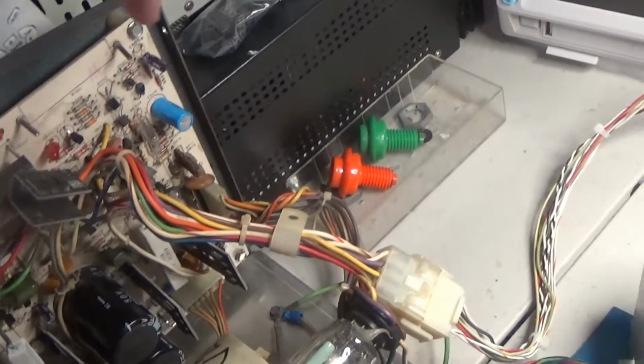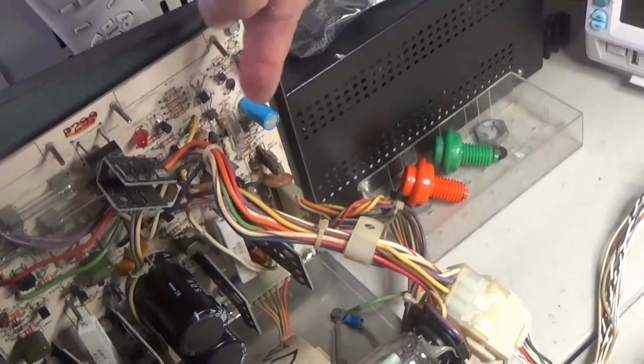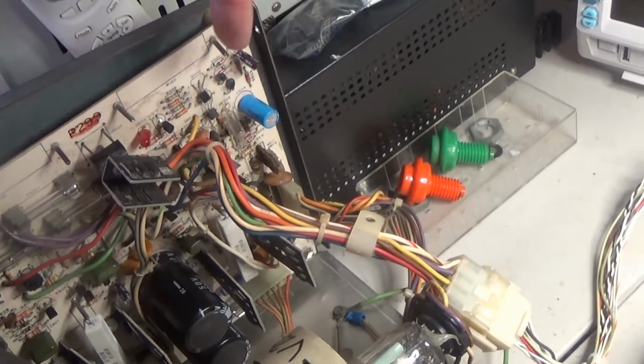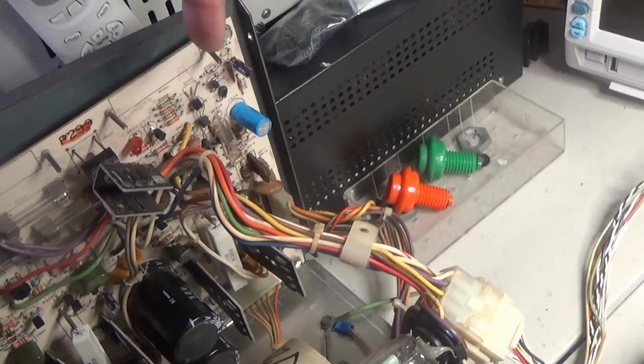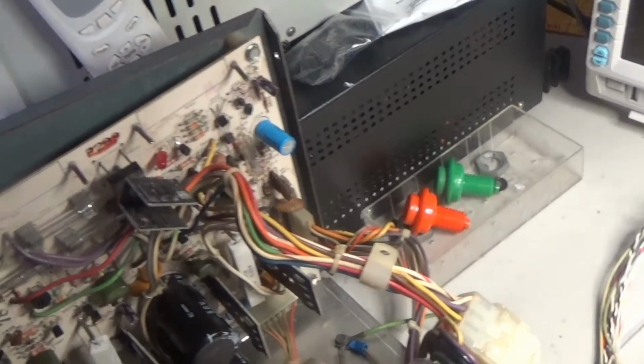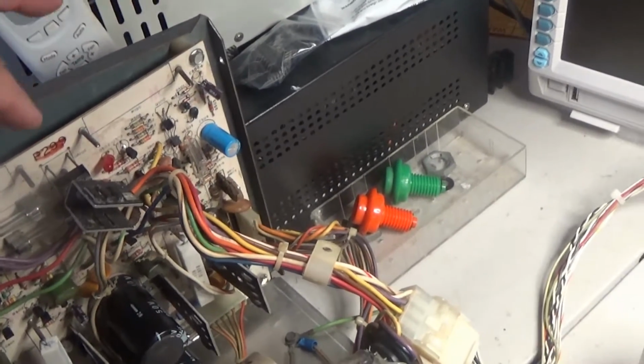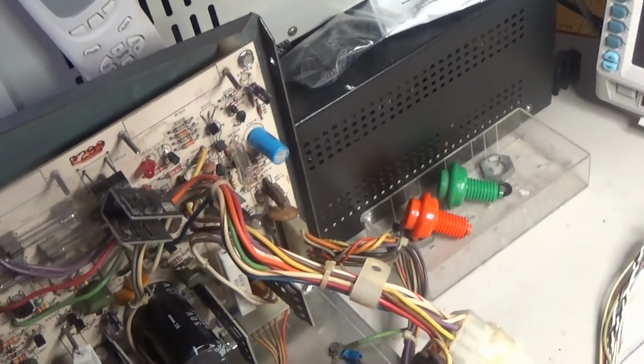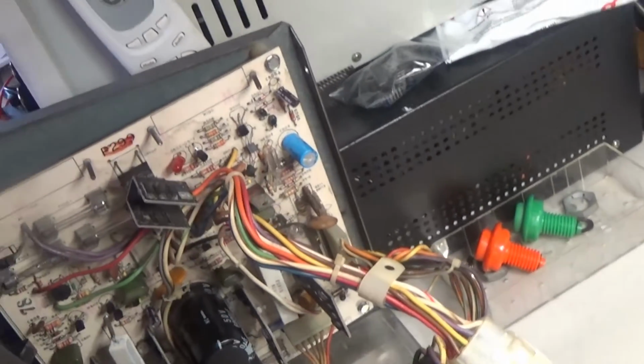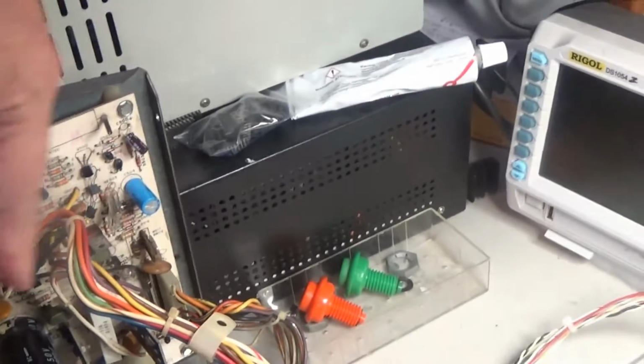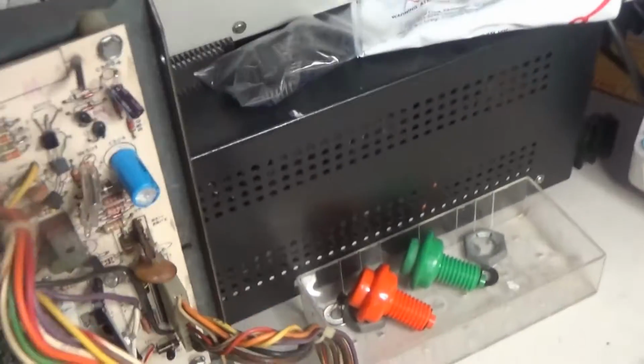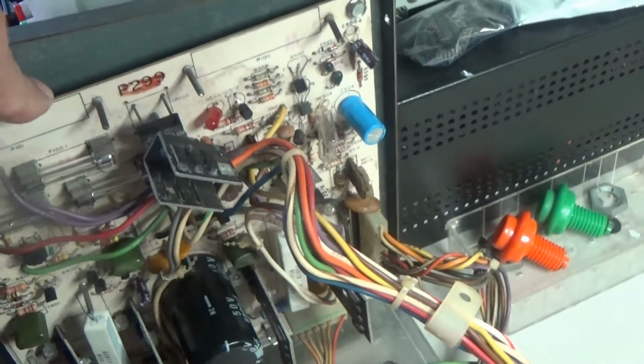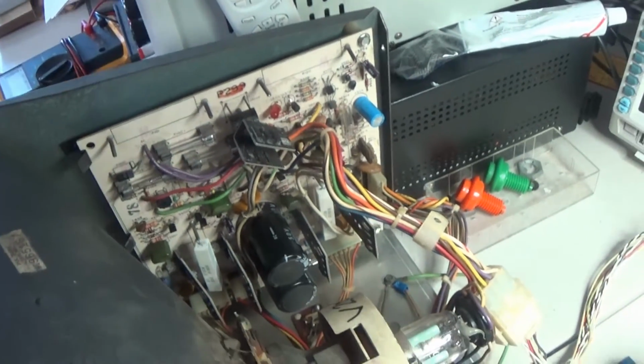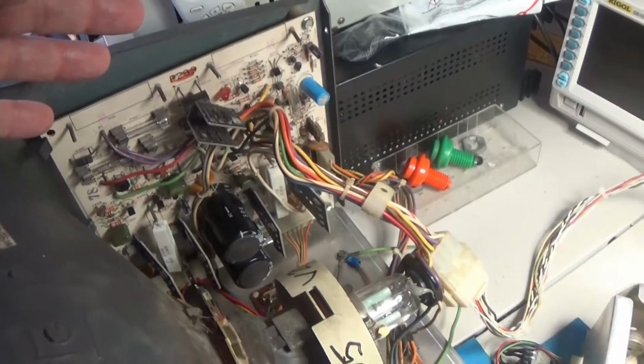The linearity pot on the Y was partially open. I replaced that linearity pot, and that really brought this board back to life. But I had to put new fuses in it because the fuses were all crusty. That's pretty much it, I believe. I replaced all of the pin connectors. I don't know if you can see in there. See that black pin connector there on the bottom? I replaced all of the headers on this to verify it's getting a good connection. So the deflection board's good to go.